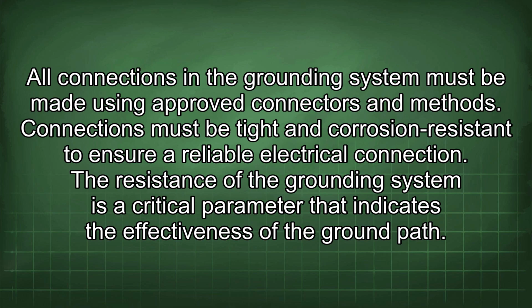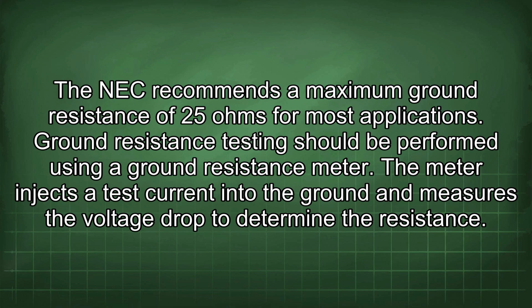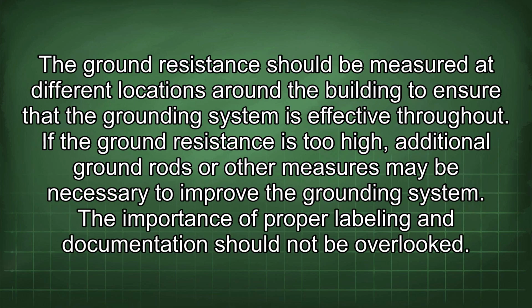The resistance of the grounding system is a critical parameter that indicates the effectiveness of the ground path. The NEC recommends a maximum ground resistance of 25 ohms for most applications. Ground resistance testing should be performed using a ground resistance meter. The meter injects the test current into the ground and measures the voltage drop to determine the resistance. The ground resistance should be measured at different locations around the building to ensure that the grounding system is effective throughout. If the ground resistance is too high, additional ground rods or other measures may be necessary to improve the grounding system.